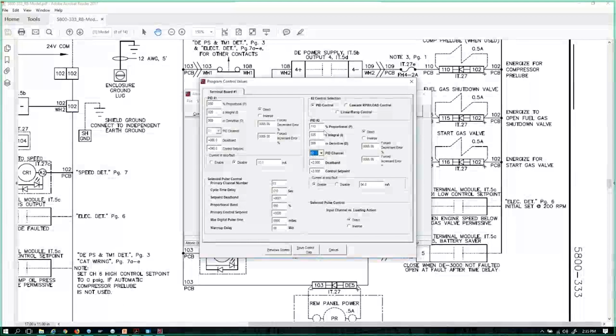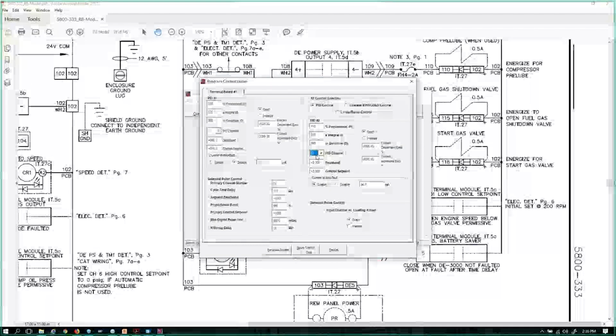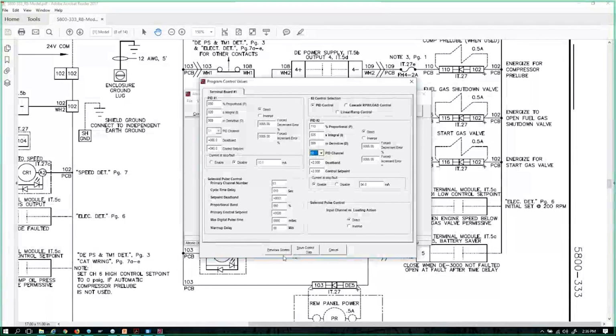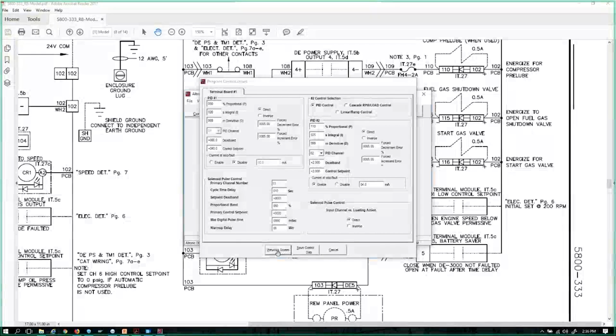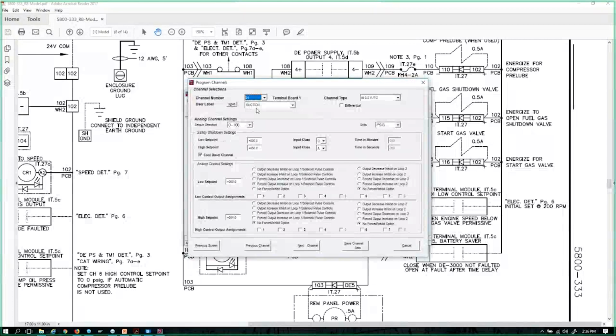So if we're going to be controlling, let's say we're going to control a suction control valve with PID loop 1 based on suction pressure, channel 1. And then with PID loop 2, we want to control a recycle valve, again based on suction pressure. With this, knowing this fact right here, all of a sudden I have to have suction pressure listed on channel 1 and channel 2 back under my channel section. Now, if I back up a little bit, I think I have that covered. Because I have channel 1 set up as suction pressure.